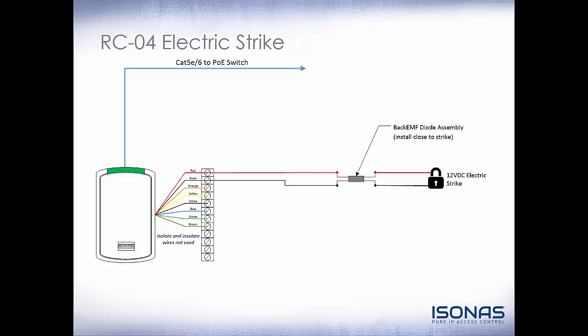Now let's take a look at some different wiring scenarios. Here is a standard RC-04 connected directly to an electric strike. The red and black wires connect directly to the electric lock. Remember, this is access control, so red and black are a logical output to the electric lock, not a power output. An electric strike does need our back EMF diode assembly, which comes with the RC-04. Also, isolate and insulate any wires not used — you don't want that green wire bouncing around and potentially unlocking the door or causing shorts.